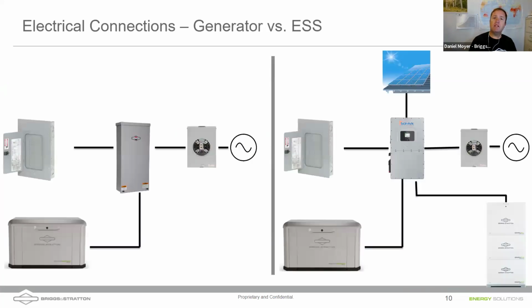So historically, how we've always done a generator, really, we have that meter socket, we have that meter can, and usually there's a disconnect there as well. We bring it into an automatic transfer switch, and then if the grid goes down, that automatic transfer switch is going to see the generator start. It's going to transfer over to generator, and we're going to support the entire load of the home on that generator.